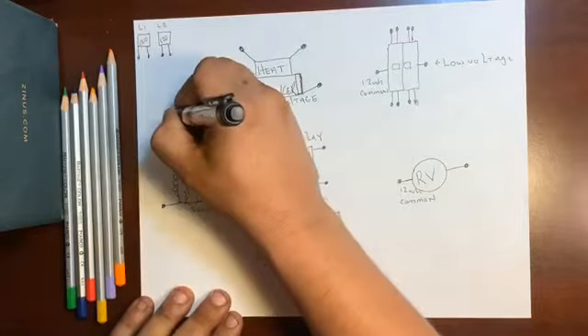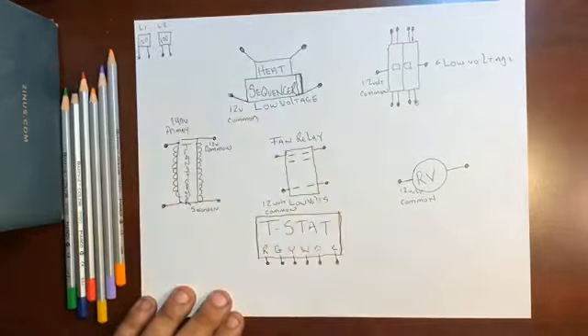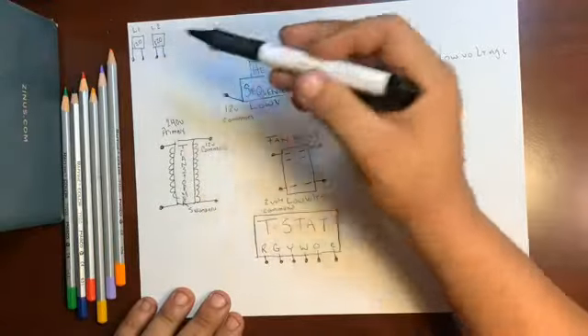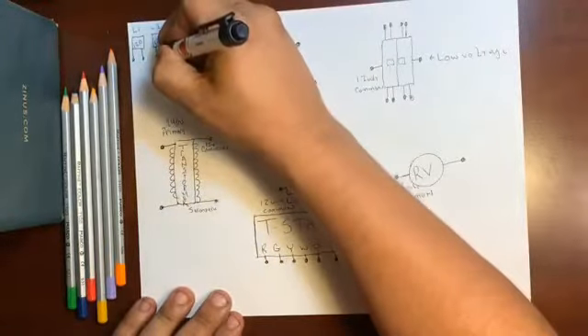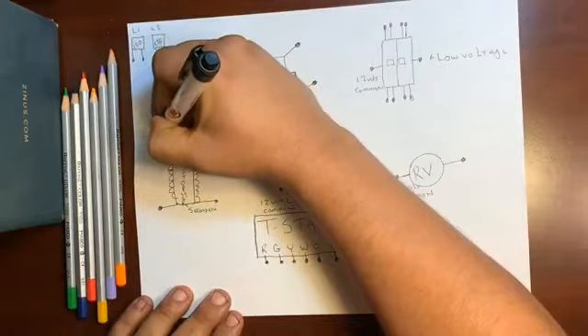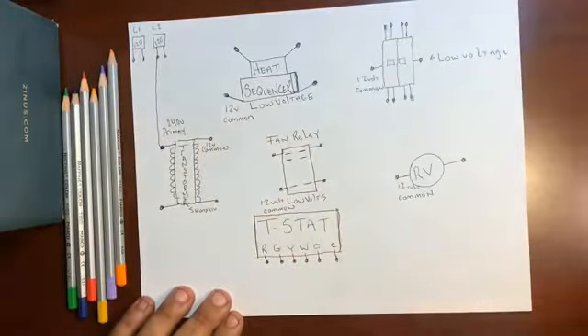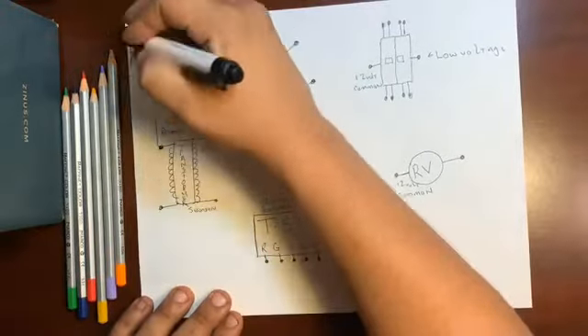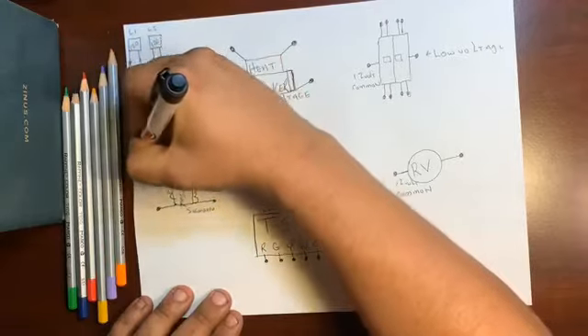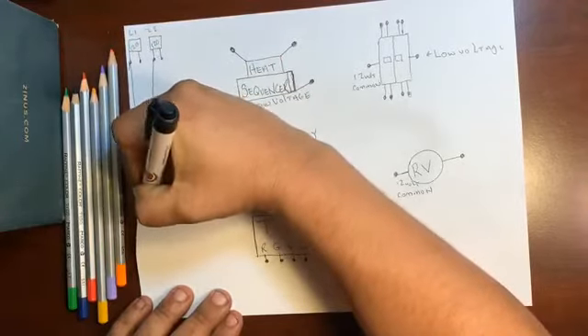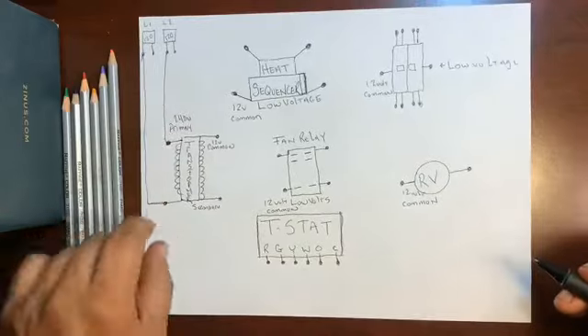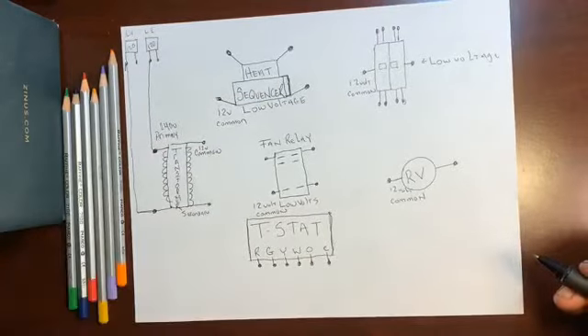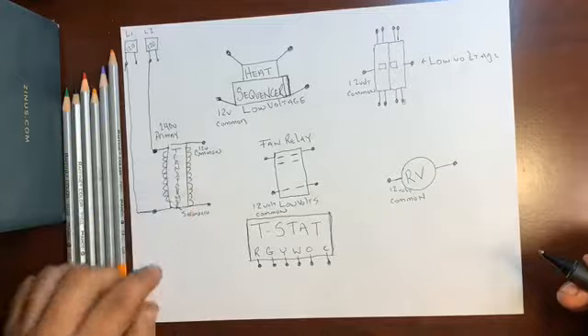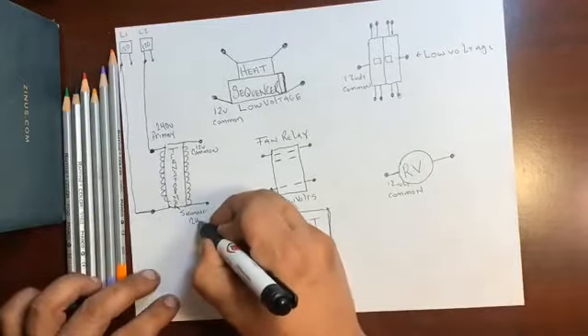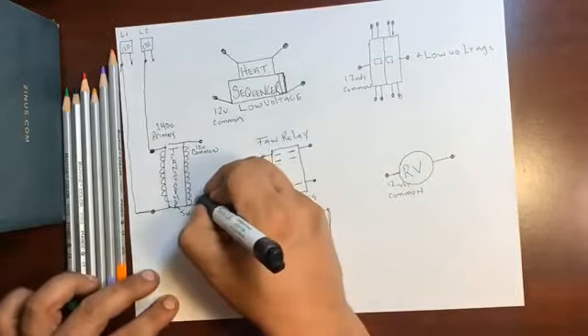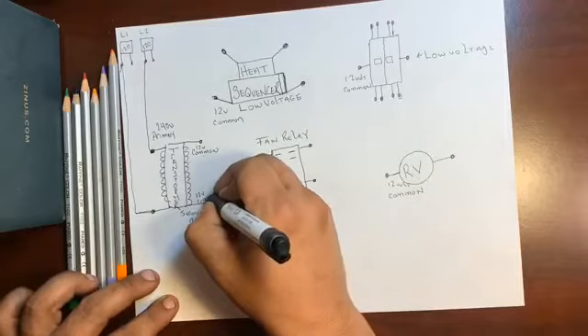We know that the primary side needs 240 volts. We're going to go up to L1 and L2, 120 apiece. We're going to bring L2 down, make a connection here, bring L1 down, make a connection right here. That's giving us 240 volts on the primary side of the transformer. What do we get? We get 24 volts on the secondary side: 12 volt common and 12 volt control.